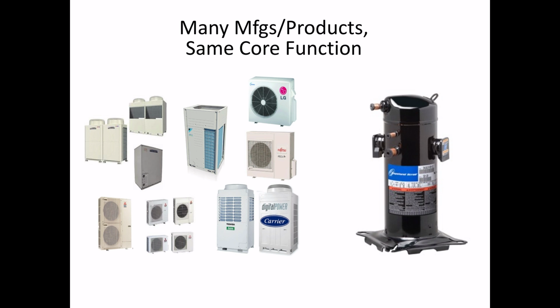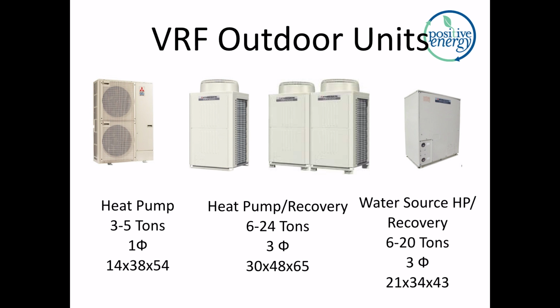Despite the differences, at the core, there's the same functional component, and it is not this Copeland scroll. I'm just using that as an illustration here of a compressor. Most of these manufacturers actually make their own compressors and their own control components. But functionally speaking, there's the same core here. It's a variable frequency compressor combined with the variable refrigerant LEV or EEV on the indoor unit, sometimes on the outdoor unit. Let's talk about some of the outdoor units now, the broad categories.